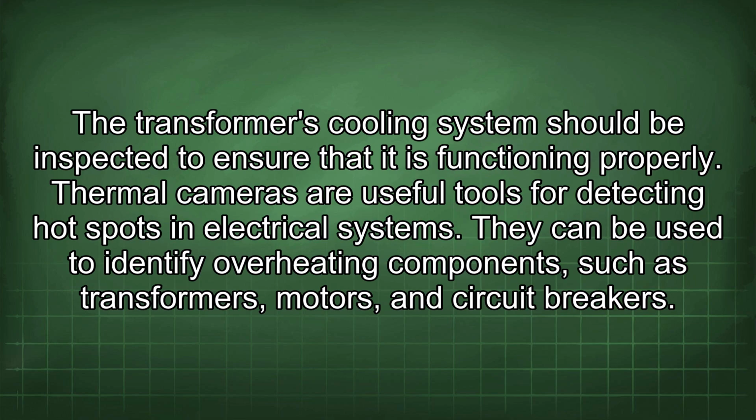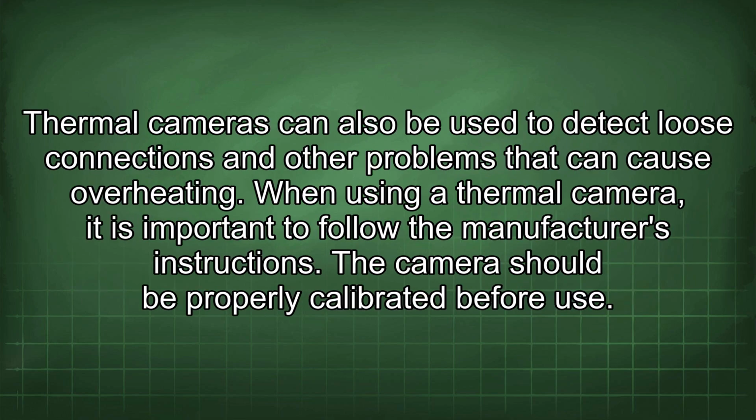Thermal cameras are useful tools for detecting hot spots in electrical systems. They can be used to identify overheating components such as transformers, motors, and circuit breakers. Thermal cameras can also be used to detect loose connections and other problems that can cause overheating.